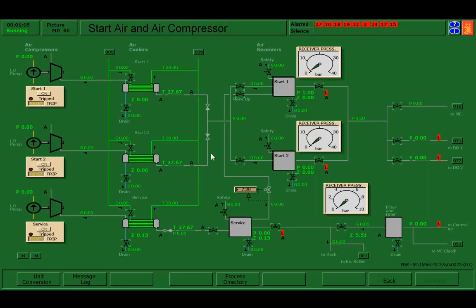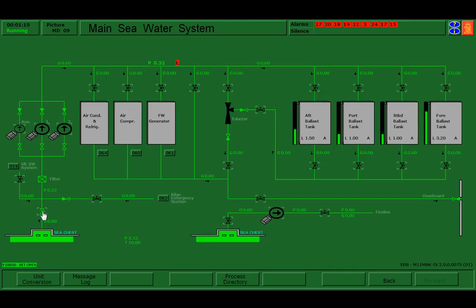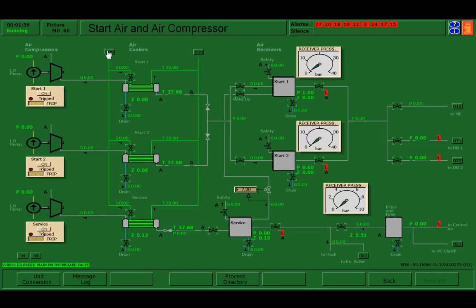Step one is going to be to get our air compressors running. Our air compressors are going to also require some cooling water supplied from our sea chest using an auxiliary pump, supplying to our air compressor, and then eventually making its way overboard. Inside the air compression system, that pathway for water feeds air cooler number 1, number 2, and my service air cooler. And I can confirm that I do have water flowing through that system.